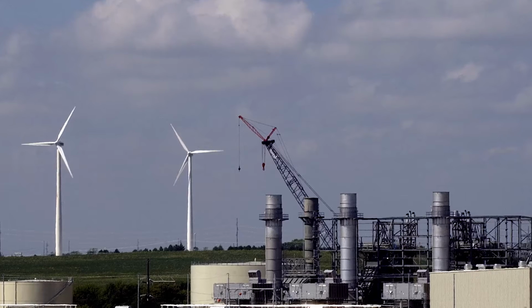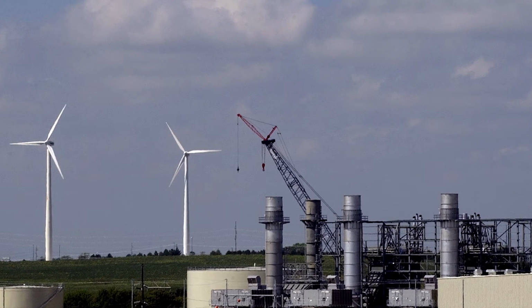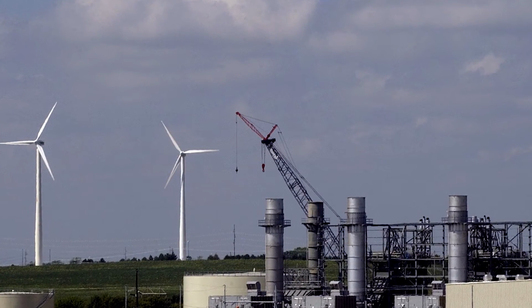It turns out that the cooling load is approximately 4,000 tons, which, as a frame of reference, a typical home might have about a 3-ton air conditioner installed on it. Looking at it, it was determined that this is something reasonable you could manageably do. At that time, that was approximately one year's load growth, so it was nice to be able to add one year's load growth for a utility our size with that process.